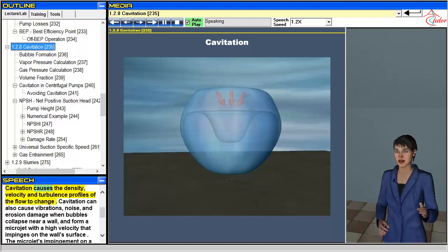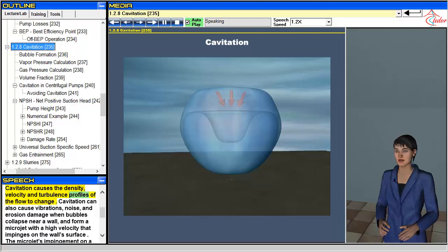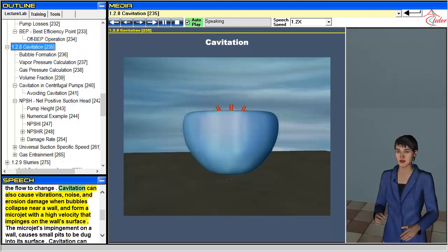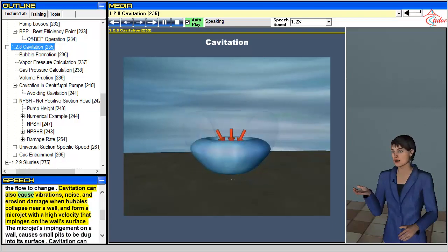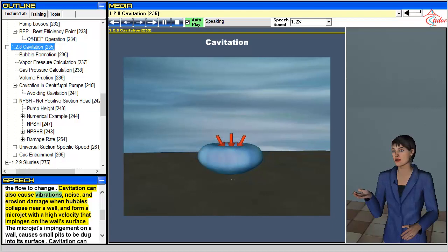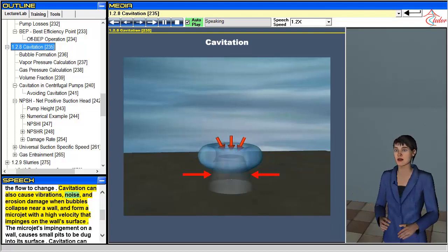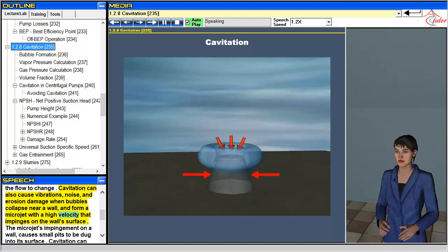Cavitation causes the density, velocity, and turbulence profiles of the flow to change. Cavitation can also cause vibrations, noise, and erosion damage when bubbles collapse near a wall and form a microjet with a high velocity that impinges on the wall's surface.